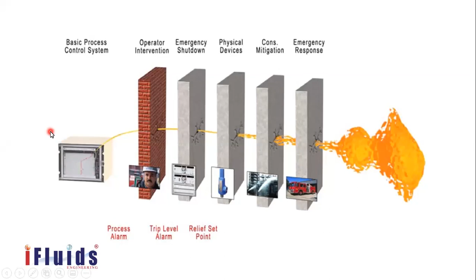Now we are thinking about the safety instrumented function. We have other protections also. You can see there is one process occurring, and suddenly a process deviation occurs. For example, you have 2 feeds, a cold feed and a hot feed coming to the system. It is a little bit of an example, everybody can understand. Suppose your hot feed coming from a CDU or any other unit got tripped. You are having only cold feed. What will you get? The level drops, and your level control will try to control. That is a basic process control system. It will try to increase the cold feed to maintain the level. Still it is not possible. It is always full open. Are there any other issues? It is not designed for that much feed. It is 100 meter cube and designed only for 50 or 60 makeup.